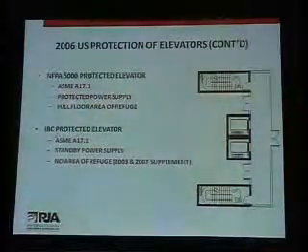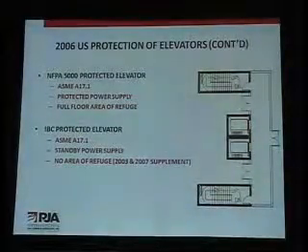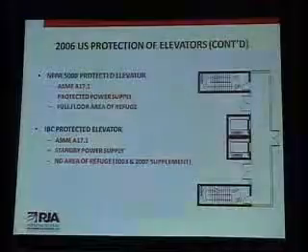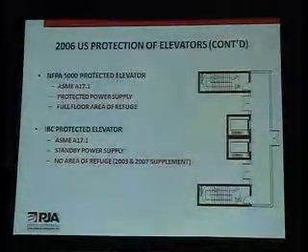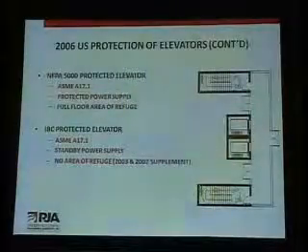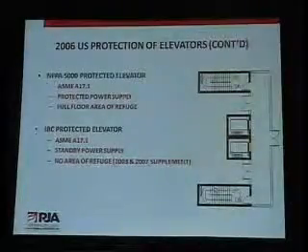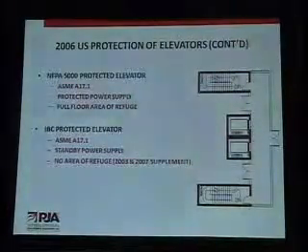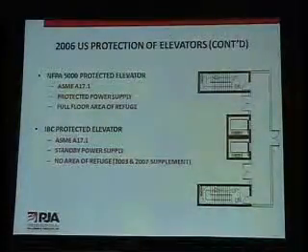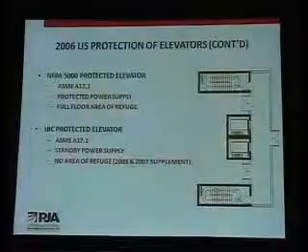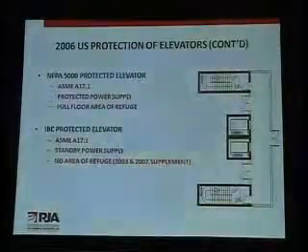So here this just demonstrates a very poor layout of an architectural floor plan. You can see that a fire protection consultant had developed this floor plan because there's no dead-end corridors. But one thing I want you to take away from this is that the stairs and the elevators have no relation to each other in this type of protection strategy. So both NFPA 5000 and the IBC do not require you to connect these two in any way, even when you're talking about elevators that are to be used for firefighter access into the building.